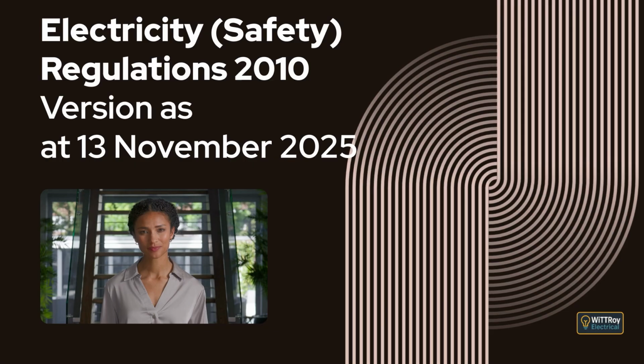Reg 63, testing prescribed electrical work on low and extra low voltage installations. This regulation explains that all prescribed electrical work carried out on a low or extra low voltage installation, or part installation, must be tested. The testing must confirm operational safety, ensure the installation or part installation is not electrically unsafe, meet the testing requirements of Regulation 59 or 60 as applicable, and, where the installation does not comply with Part 2 of AS/NZS 3000, follow the verification or testing process set out in the certified design. It then explains that this testing requirement does not apply where the work is done under the domestic wiring exemption in Section 79 of the Act, unless testing is required to comply with Regulation 57.